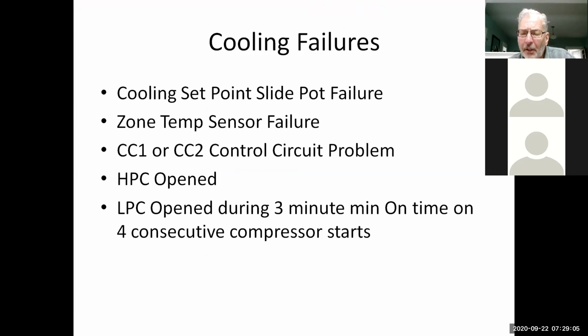Now, it's also going to look for contactor 1 and contactor 2. And if those coils are bad, it will cause you some problems too. So when you're working on these, you probably want to ohm out the contactor coils, and they should be between probably 6 and 10 ohms resistance. If they're above that or below that, a lot of times the board won't recognize it. The amp draw won't be correct, and it will lock that circuit out. It does that to protect the contactor. So the contactor needs to be a certain value.